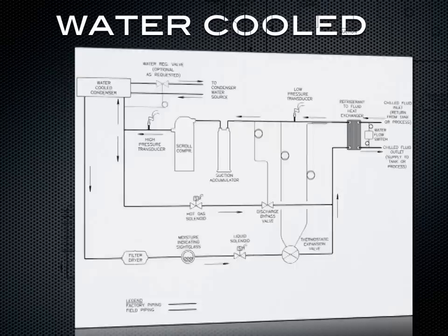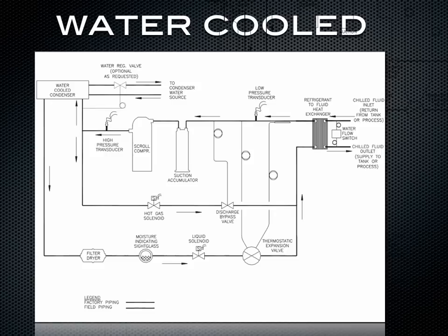Let's go over the water-cooled refrigeration system diagram. The first thing you're going to notice is it looks almost identical to an air-cooled chiller. The difference is where the heat is rejected through the condensers. On an air-cooled chiller, the heat is rejected through fans out to the atmosphere. On a water-cooled chiller, the heat is rejected to a cooling tower, building water, or some use geothermal.